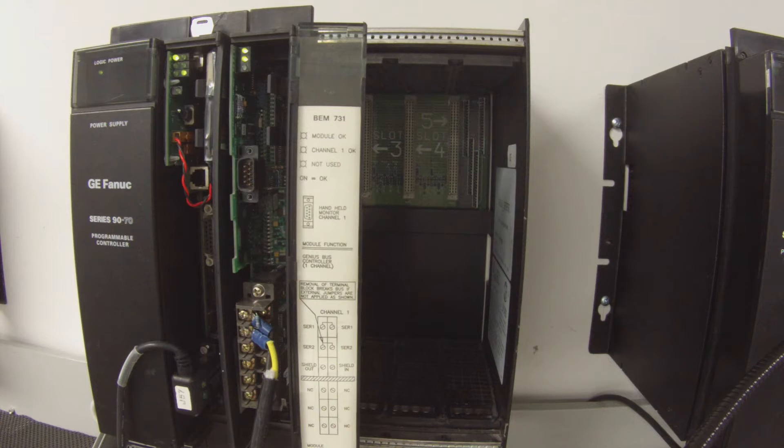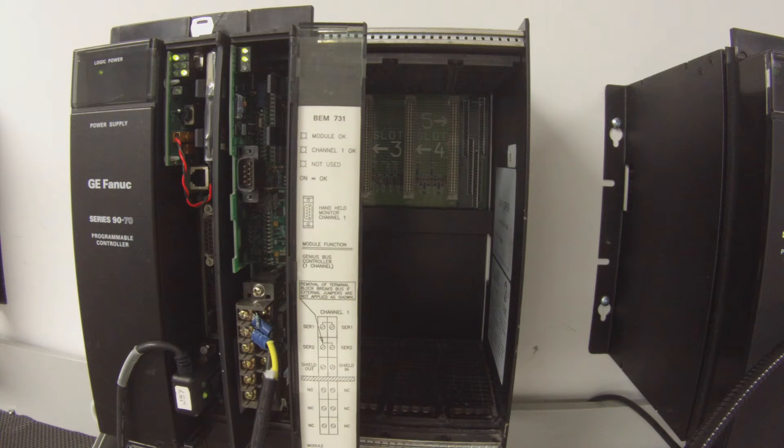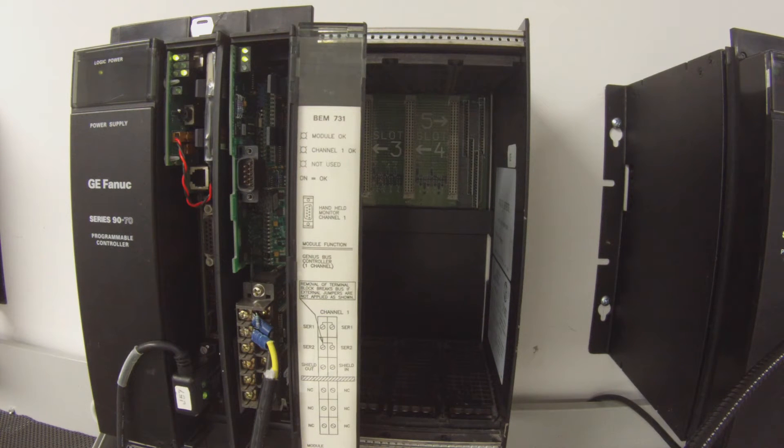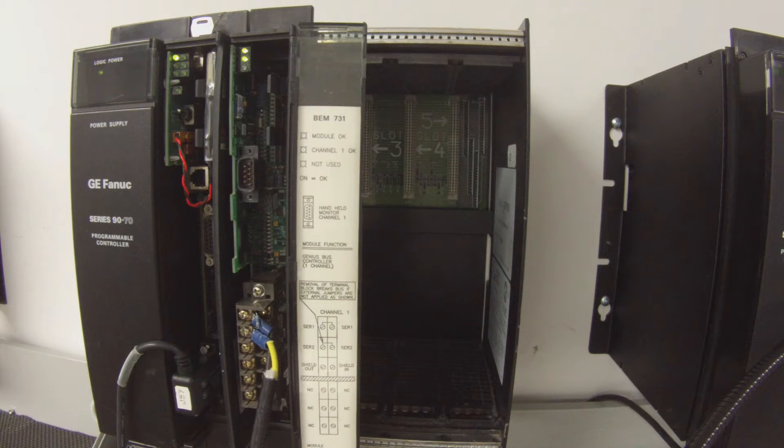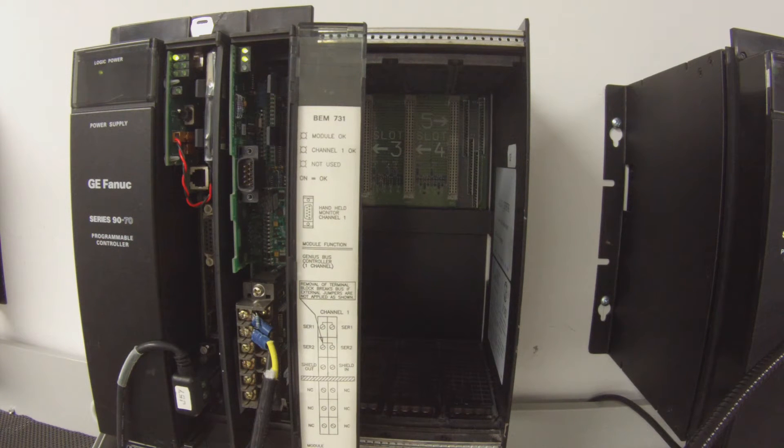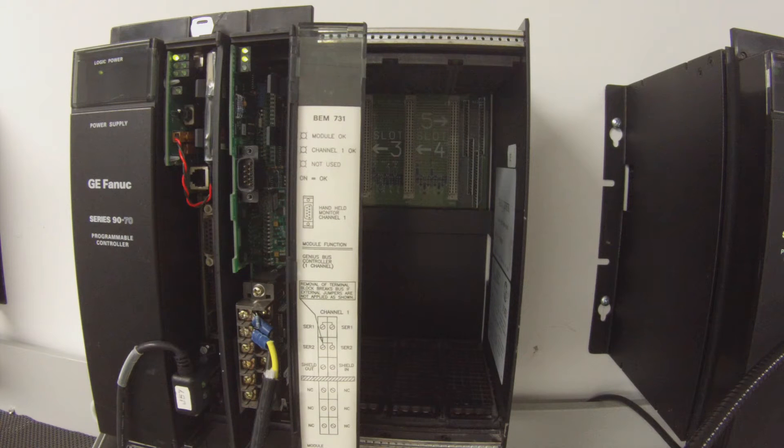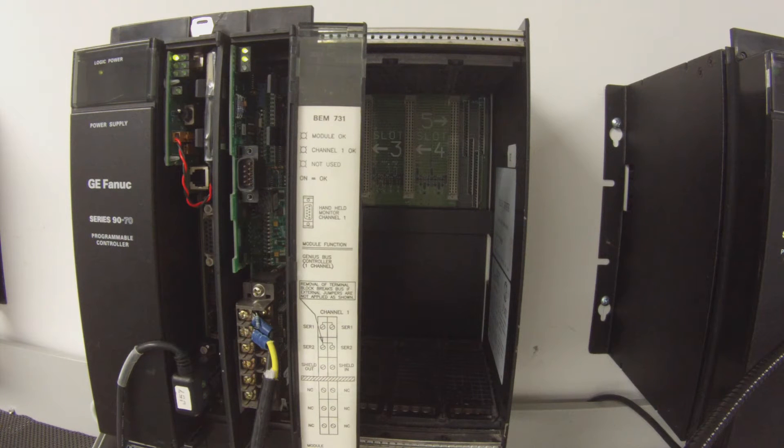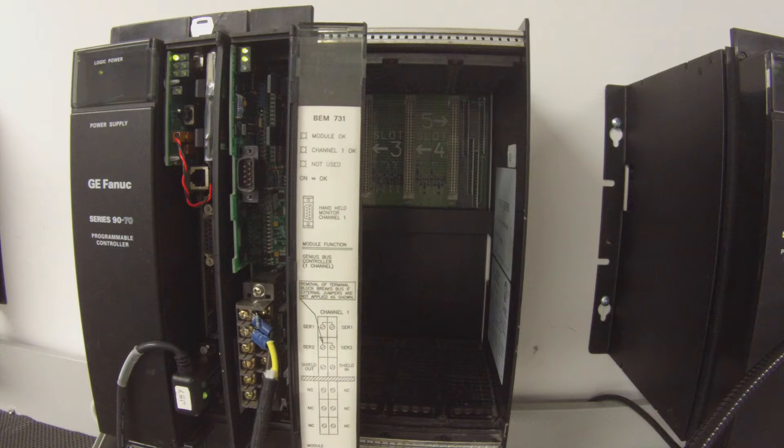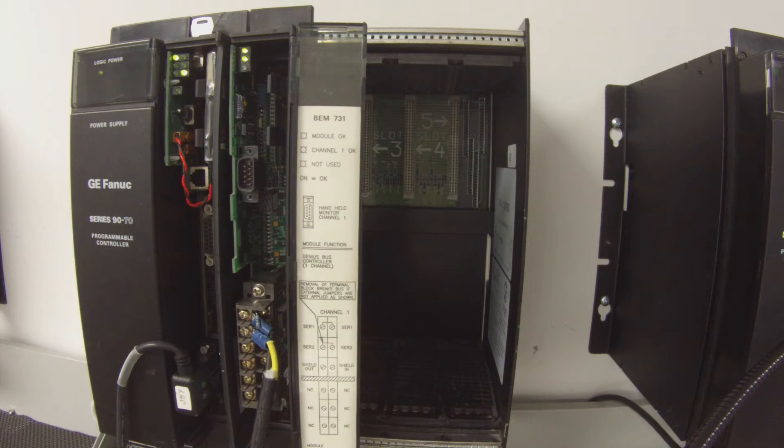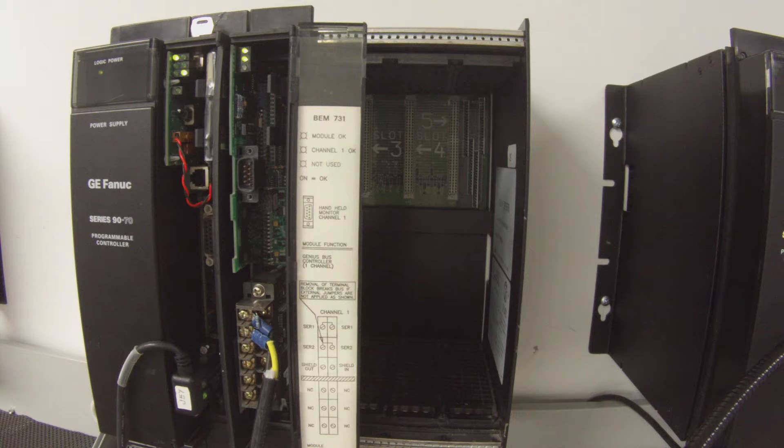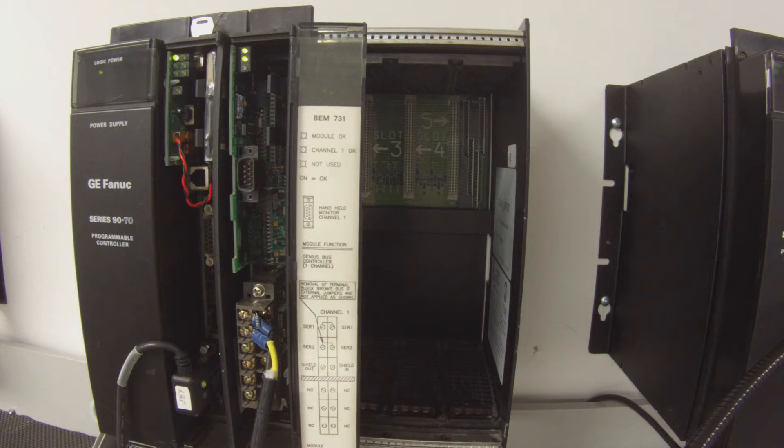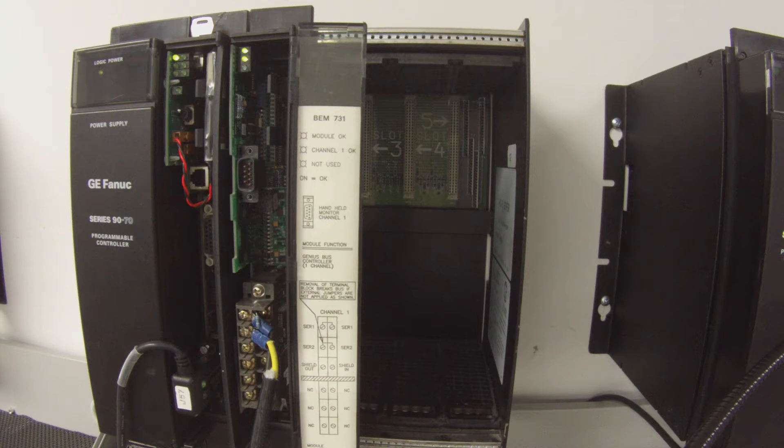Slot number two, I'm choosing an IC697BEM731. And when I do that, there's a device that drops. What you want to do is right-click on slot number two. A window will pop up, and you want to go to add genius device. Serial bus address one is what it's going to ask you first. That's fine. You use one.